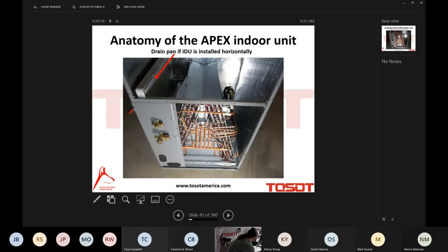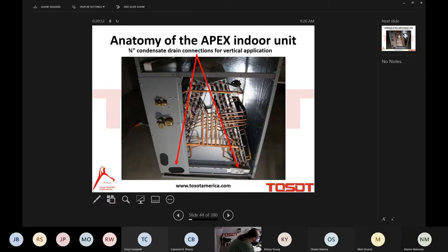Okay, let's move on. The drain pan of the indoor unit, there are two, one positioned for the traditional vertical application, but the indoor unit, guys, can be placed in a horizontal position. The drain pan for the horizontal application, I'm pointing to it there in the picture, is from the factory in the air inlet out left, return air right configuration, but you can reverse that in the field. And I'll show you how to do that as we move forward. So that pan can be moved from this side to literally reverse the discharge out, return air in configuration.